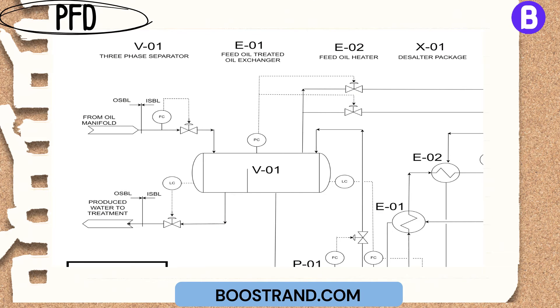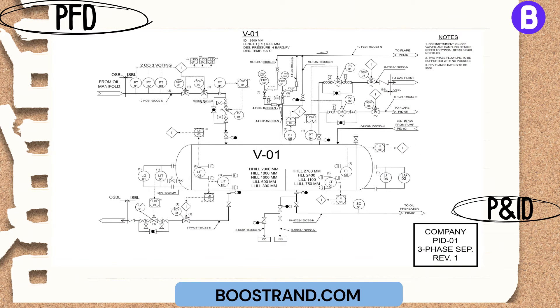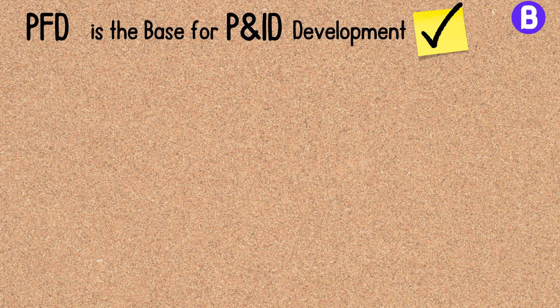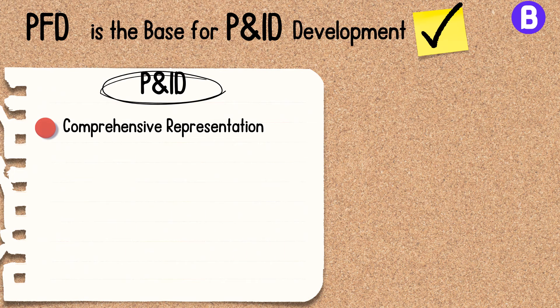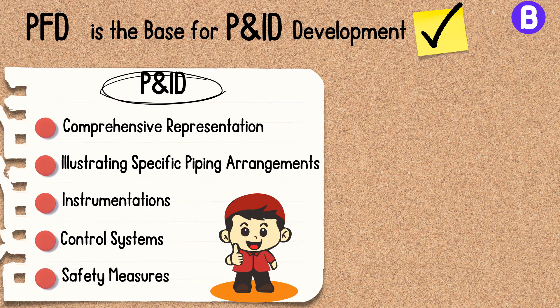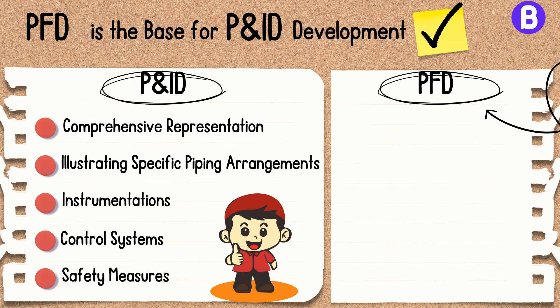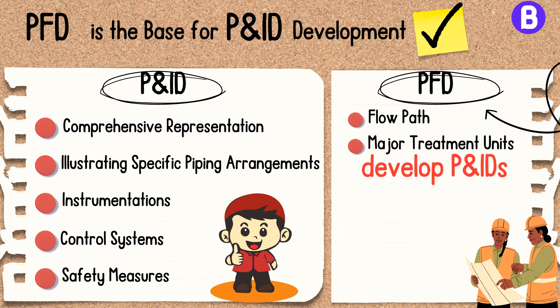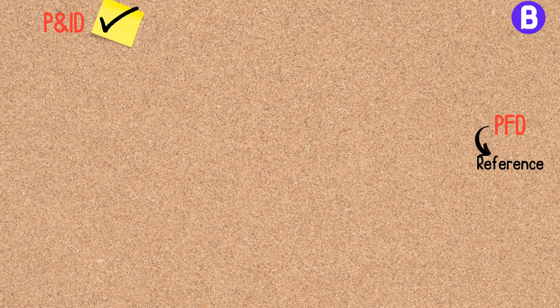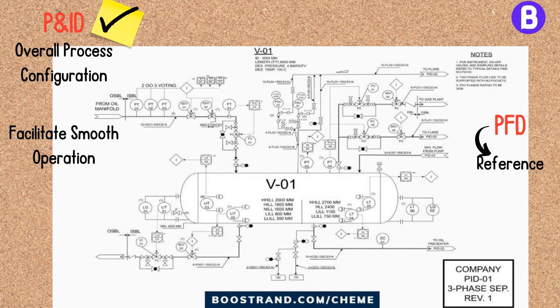Based on this PFD, engineers can develop P&ID. The process flow diagram serves as the foundation for creating detailed piping and instrumentation diagrams (P&ID), providing a more comprehensive representation of the process, illustrating specific piping arrangements, instrumentation, control systems, and safety measures. For example, a PFD for a wastewater treatment plant would show the general flow path and major treatment units, and from it, engineers develop P&ID outlining precise piping connections, instrumentation locations, and control loops, ensuring the P&ID accurately reflects the overall process configuration.